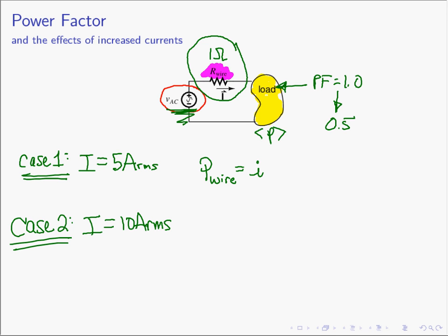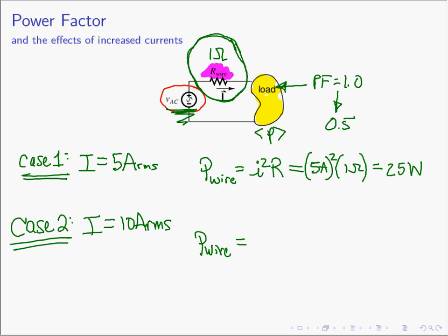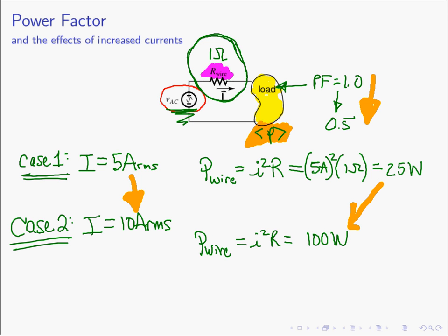A resistor has a power absorbed of I squared R. In the first case with one ohm resistance, we have 5 amps squared times one ohm, absorbing 25 watts in the wire. In the second case, I squared R gives us 100 watts absorbed. By simply worsening our power factor from 1.0 to 0.5, the current doubled, so the power absorbed by the utility's wires went up by a factor of four because of the squared term.